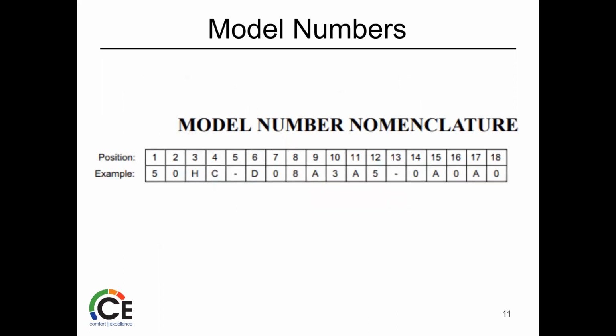So again, the model number tells us a lot. It seems like just a long drawn out number, but every one of these spaces in this 18-digit model number tells us what type of unit, what the voltage of the unit is, what components it may or may not have. So we don't have to waste time gathering that info. You've already given me the model number, and I can see, okay, this is a unit that definitely has this type of economizer, this type of control box or whatever. And then a lot of times I can answer your questions faster, or the group can.